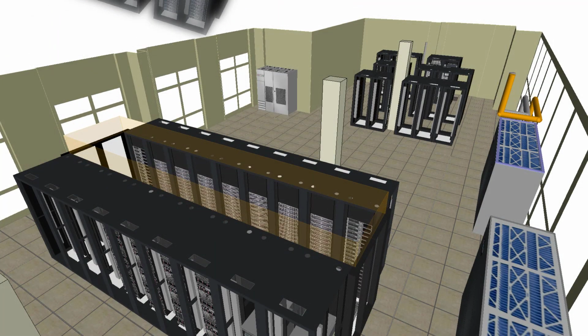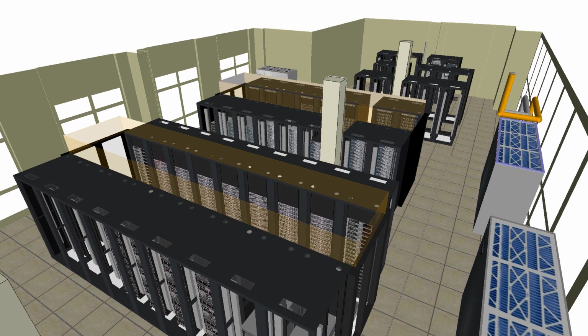However, after the installation, two IT units in the adjacent aisle lost cooling capacity and put IT reliability at risk. This outcome was missed because the detailed response of the cooling system, including airflow and cooling system operation, was overlooked.